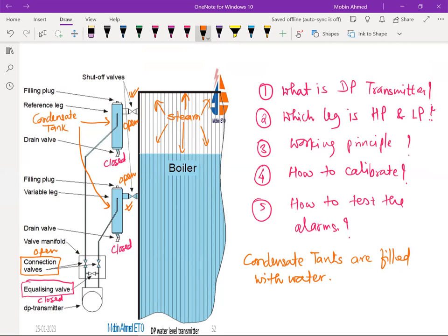Maybe you talked about the shrinking effect and swelling effect because of that. Sorry? You are telling me this shrinking effect and swelling effect is on the water level only, maybe. No. I am asking which leg, like this one is a leg and this leg, which leg is going to be the high pressure leg and which is going to be the low pressure leg. It is nothing to do with the swell and shrinkage effect. So is it possible it will be changing all the time? Will it be changing, like when the water level is low, the pressure will be low there, and when the water level is high, the high pressure side will be there?